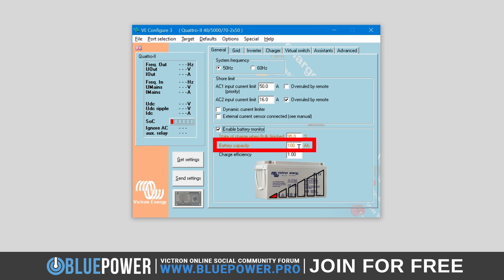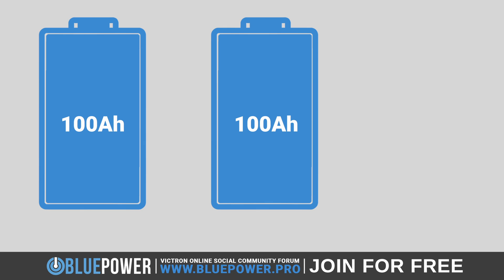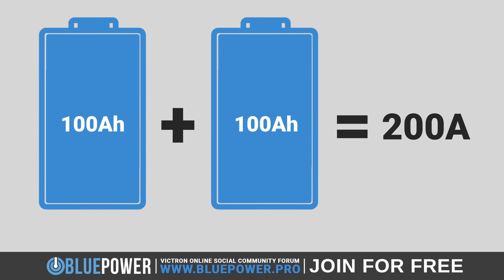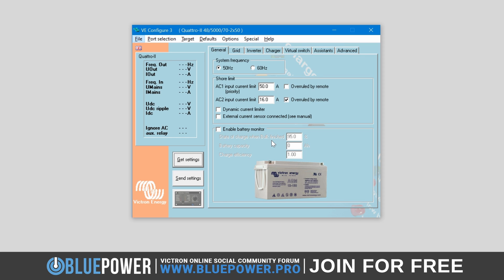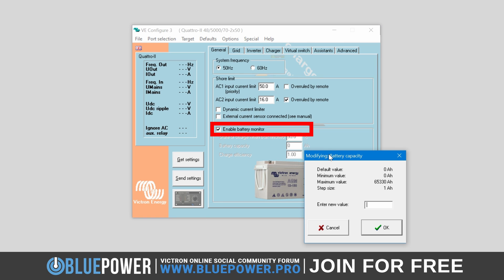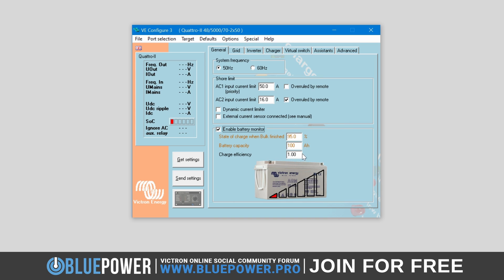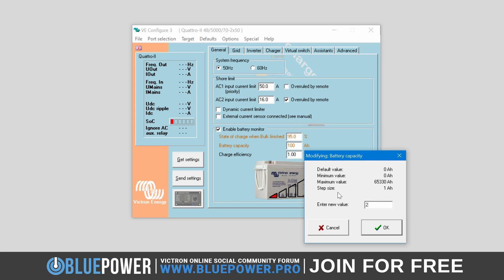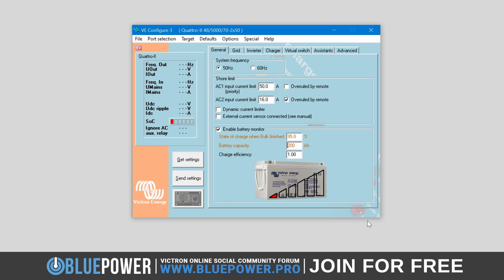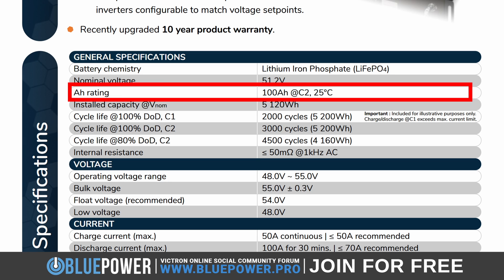Battery capacity is simply the total capacity of the battery or battery bank connected to the system, adjustable in amp hours. For example, if you have two 100 amp hour batteries, this should be set to 200. This setting is critical because it allows the monitor to accurately calculate the state of charge. When enabling the battery monitor, a pop-up window will appear asking you to set the battery capacity and will not enable until one is set. For iron phosphate batteries, this should be the nominal capacity as specified by the manufacturer.